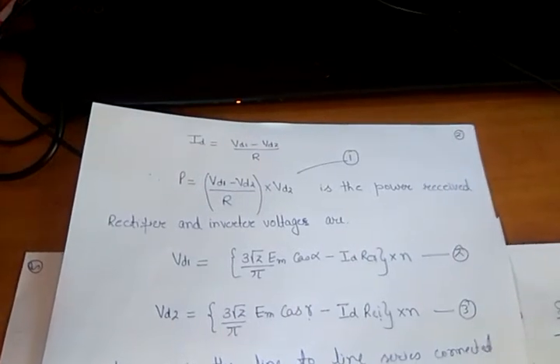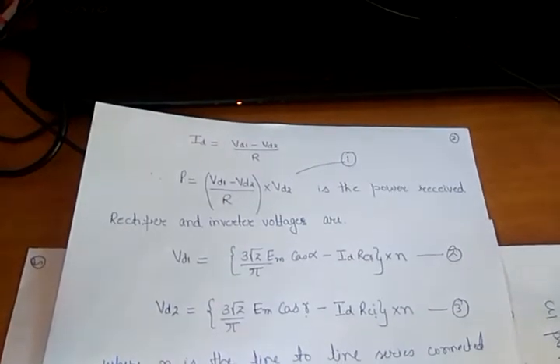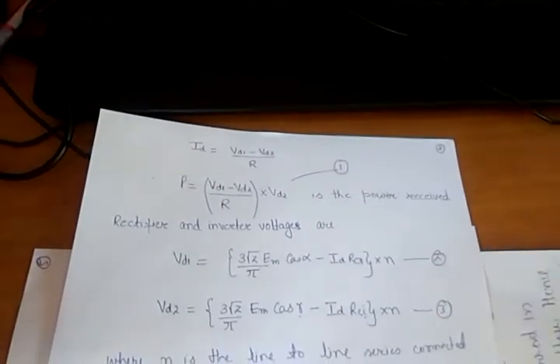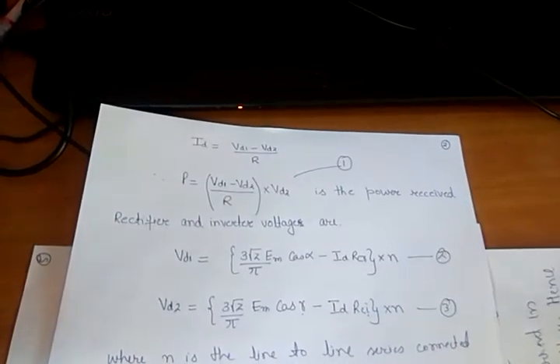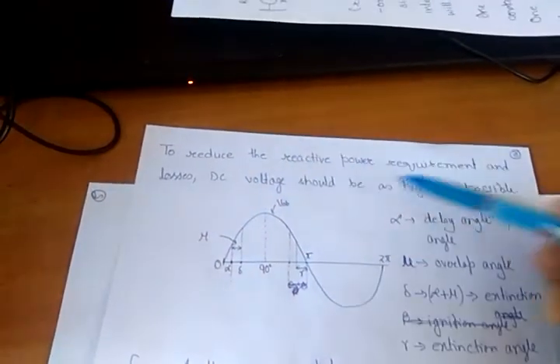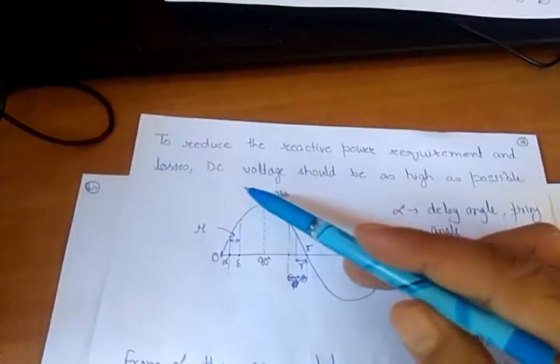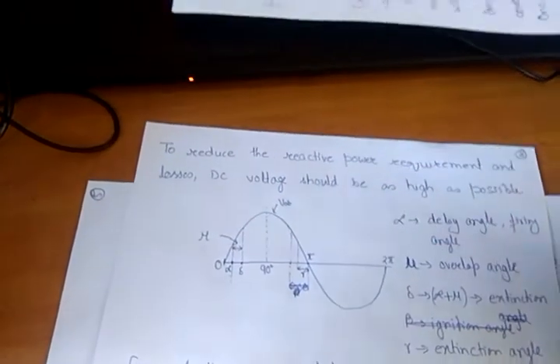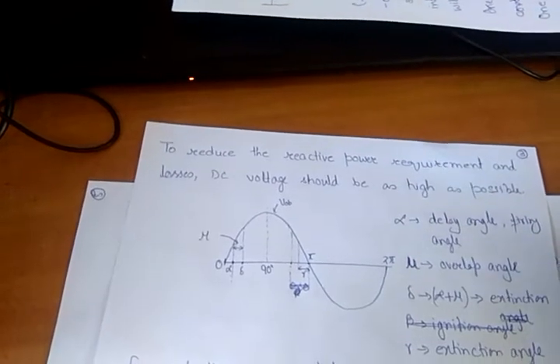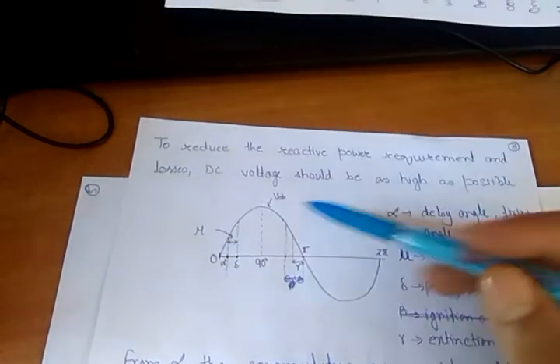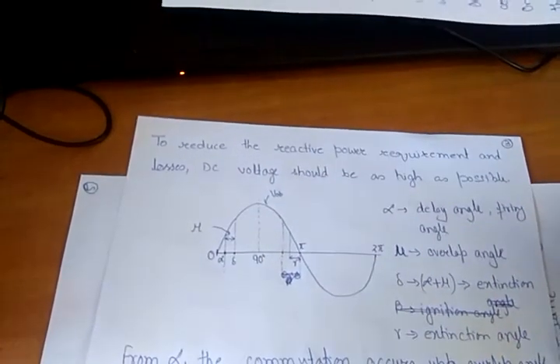In an HVDC system, huge reactive power is required at converter terminals, and there are losses due to harmonics and other things. The objective of the controller is that losses as well as reactive power requirement should be as low as possible. This can be achieved by keeping the DC voltage as high as possible — the smoother the DC voltage, the fewer harmonics, so high DC output voltage means low reactive power requirement and losses.